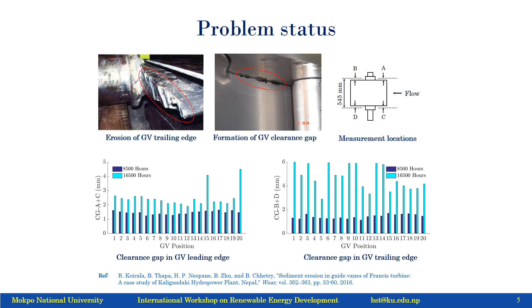Why does this increase so rapidly, and what does it do to the other components? So I set up with the hypothesis, what we call the dry clearance gap. That is, the walls or the cover plates and guide vanes have a small clearance gap, around 0.1 to 0.3 millimeters, that is needed for the guide vane to move. But the flow with the sediments slowly erodes the material and causes the increase in the gap of the guide vane. And due to the pressure difference of the guide vanes between the pressure side and suction side, the leakage flow starts from the increased clearance gap, and this leakage flow disturbs the main flow at the runner, and this disturbance causes reduction in efficiency of the whole turbine and also increase in erosion of the runner and other components. So this is my hypothesis.